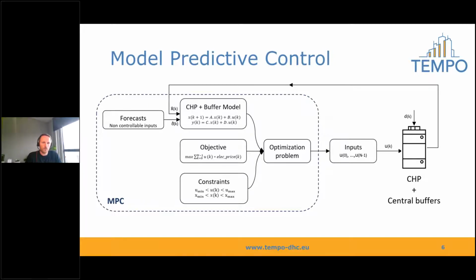Once we have these inputs for the model, we apply an objective to this model. And as just said, the objective here is to maximize the revenue from the sold electricity. Besides this objective, we also need to put in some constraints, because the system has constraints in which it has to work. For example, we have the CHP, of which at this time only one is in operation, and it is able to generate 250 kilowatt thermal heat output. One constraint is that it's non-modulating. So we can either switch the CHP off or switch it on at full power. That's the only possibility we have.